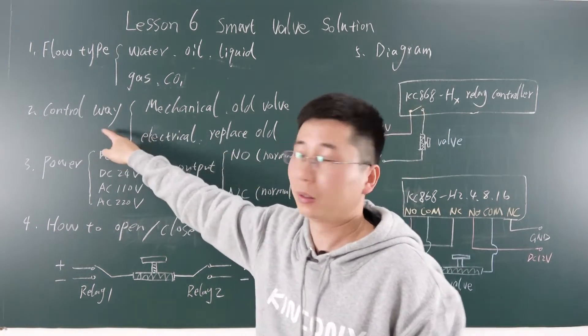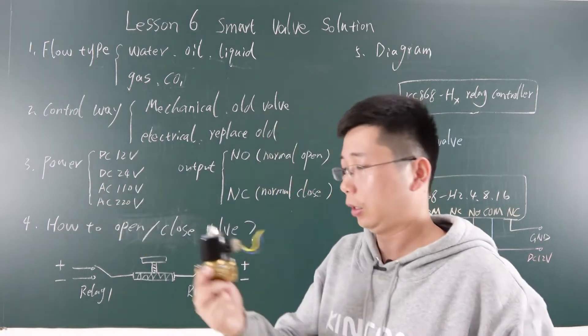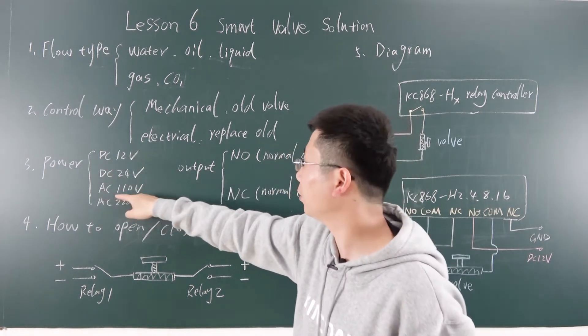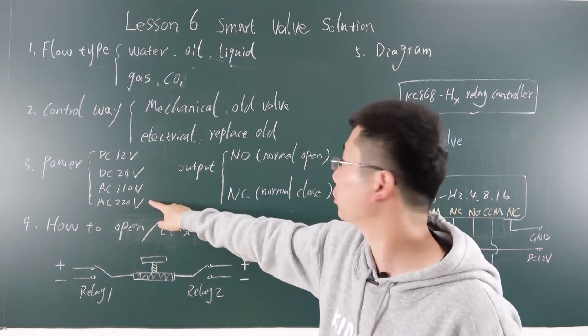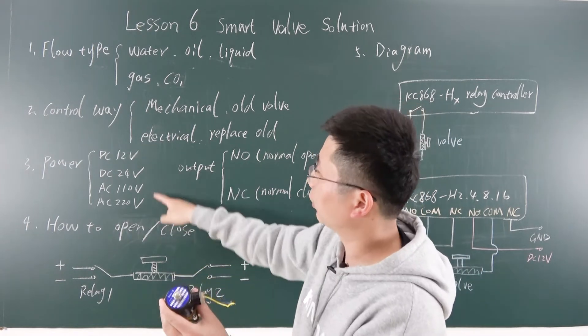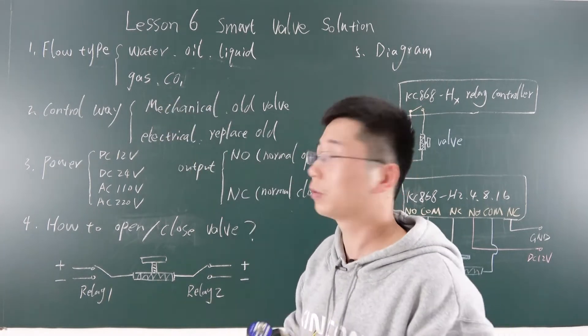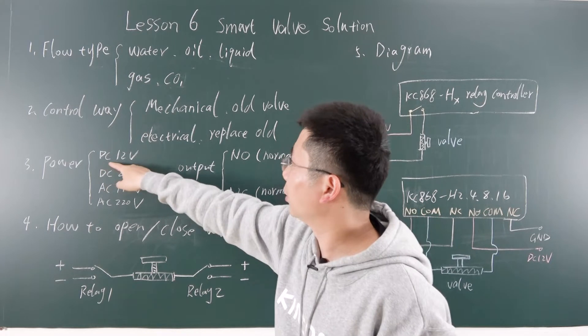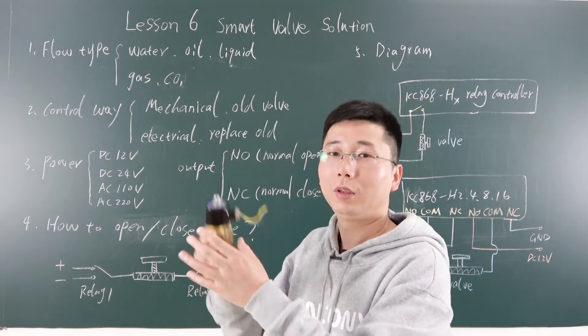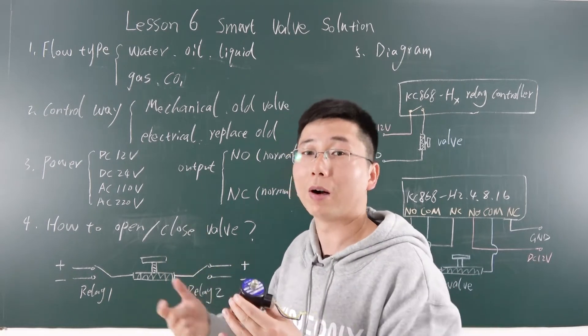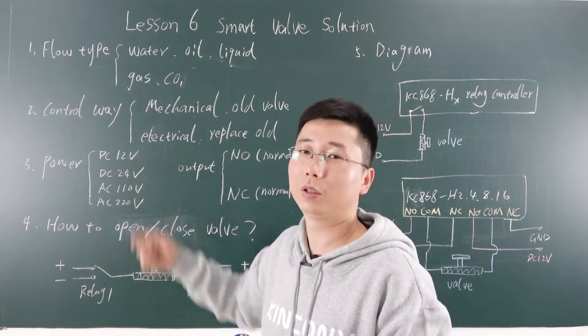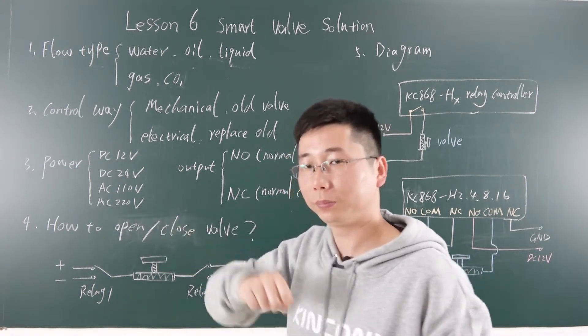There are also different power supply options for the device. Maybe you have DC 12V or DC 24V, or AC 110V or AC 220V — different voltages you can choose. If you use the gas type, because it is dangerous with high voltage, you'd better choose the low voltage. Low voltage is better for safety. But if the valve is very big and needs more power to drive it, maybe you need AC 220V. If you can choose low voltage, just choose low voltage.